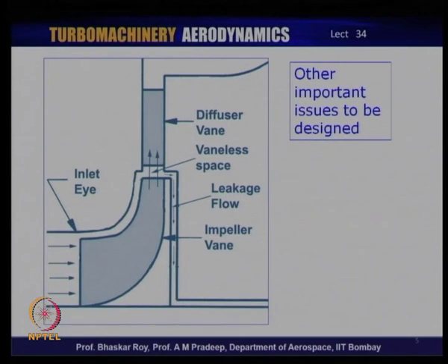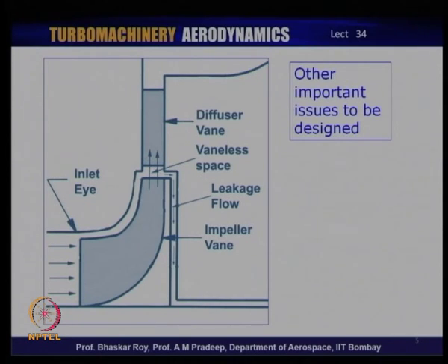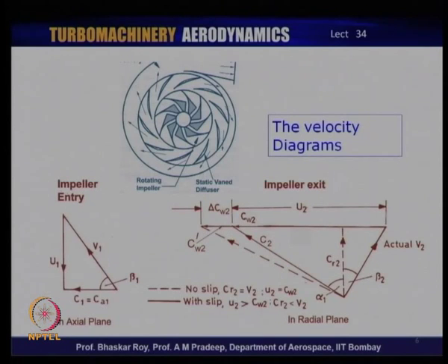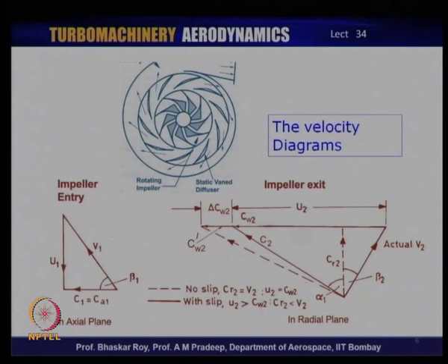Some of these geometric parameters — the small gap that needs to be left all around the impeller, and very importantly the vaneless space between the rotor and the stator — need to be decided by design so that the flow during operation is always under some amount of control, avoiding losses and various instability-related issues. Let us now take a look at the velocity diagrams that are operative at the entry and exit of the impeller — the most important element that needs to be designed.